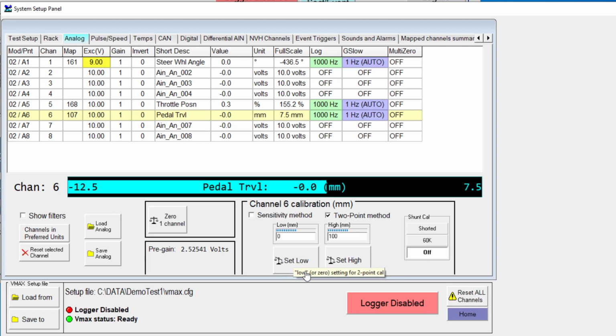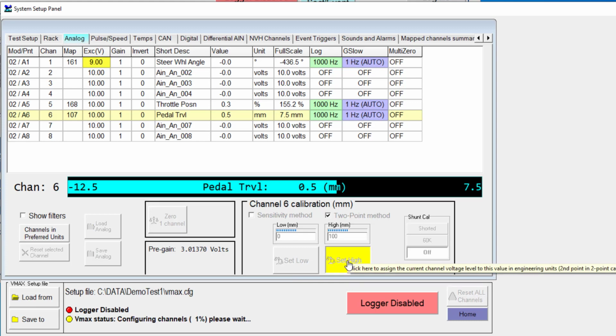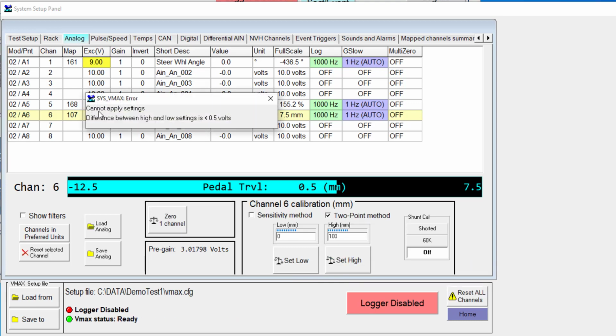Something I did want to show is, if I just apply a little bit of input to this sensor and I try to hit the set high, you notice it's going to tell me that the difference between the high and low settings is less than half a volt. So in order to accommodate a calibration, we do require that we see at least a half a volt DC change in between your two different calibration points.